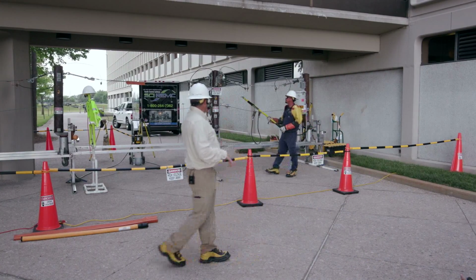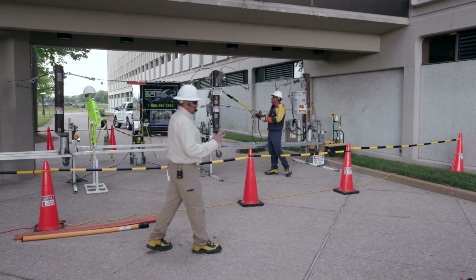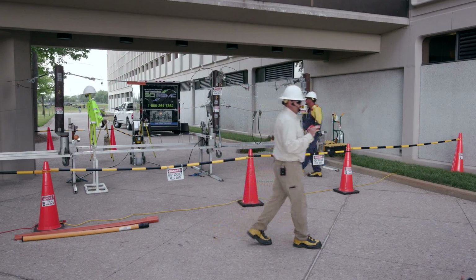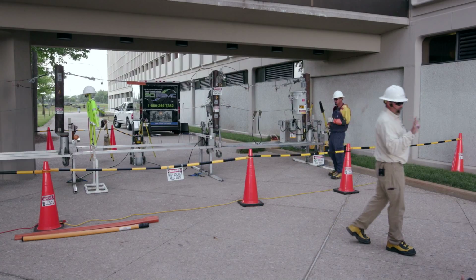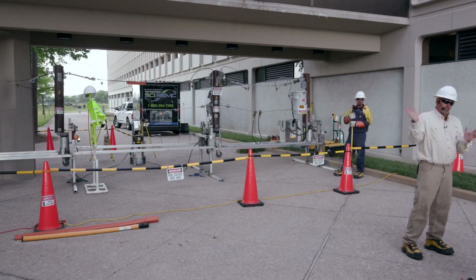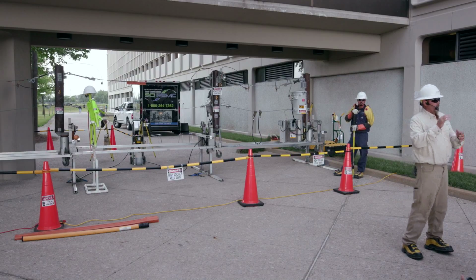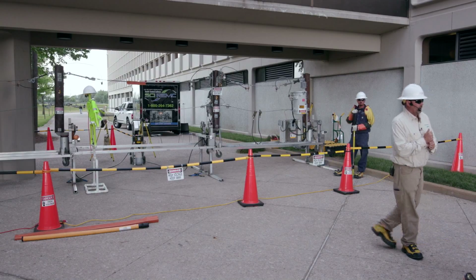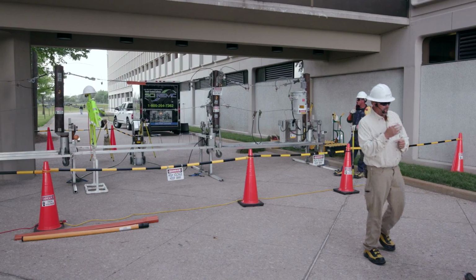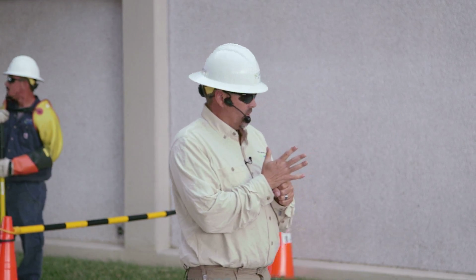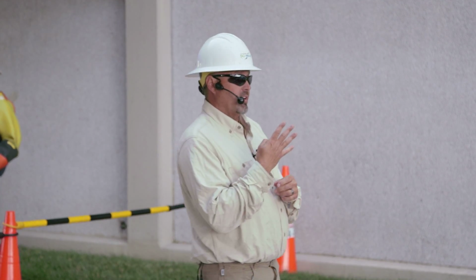All right, so that's a one-shot device. The device on the back of pole 2 is an recloser. It's very similar, but it's going to operate 4 times. So say a tree falls on the power line — that recloser is going to operate 4 times. It's going to click, open up, click, open up, and do it 4 times.